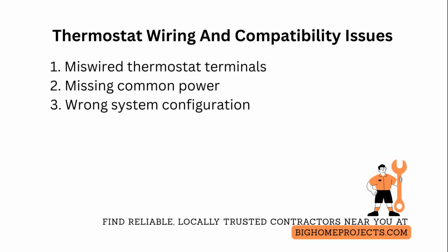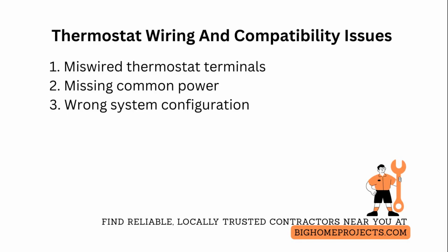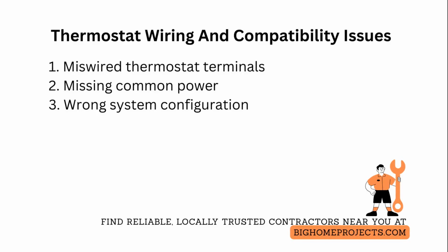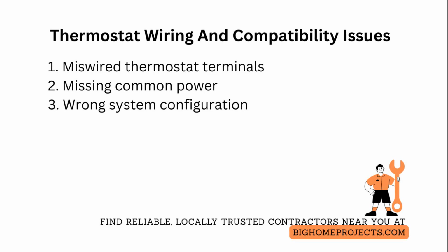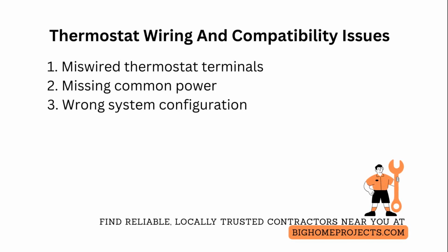The third typical problem is wrong thermostat mode or configuration settings for heat pump versus conventional systems. Correct this by setting the thermostat to the correct system type, verifying reversing valve polarity, and testing the reversing valve activation while monitoring voltages.